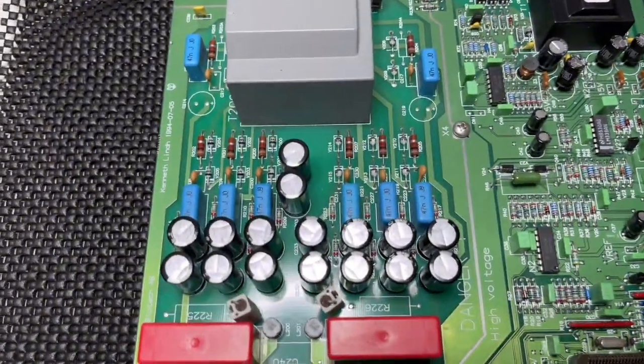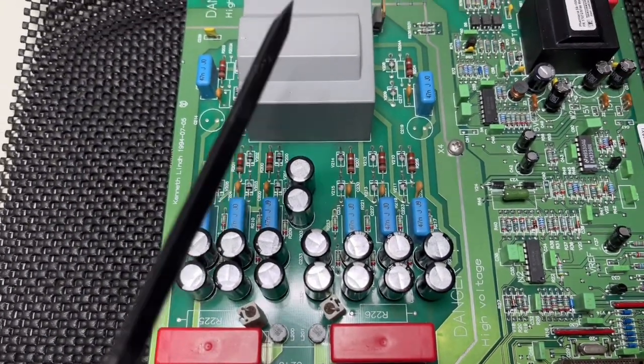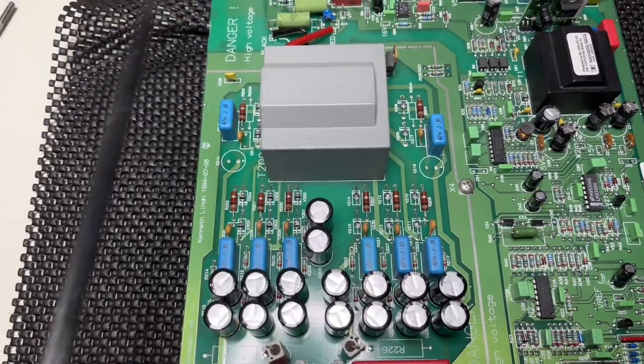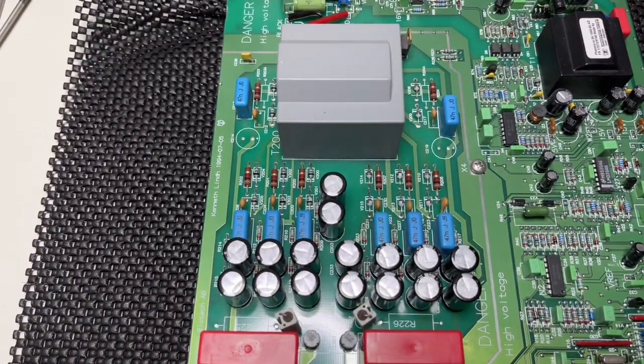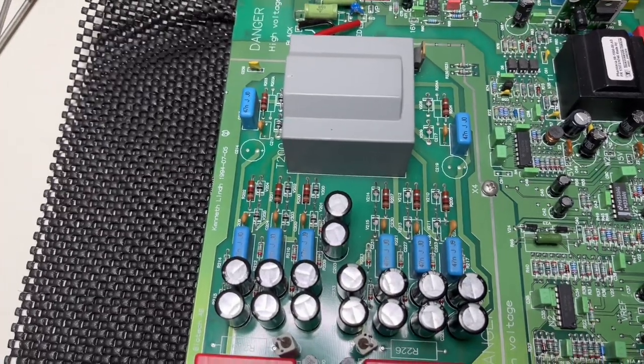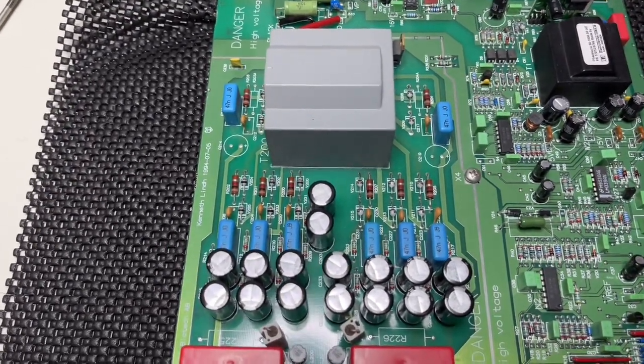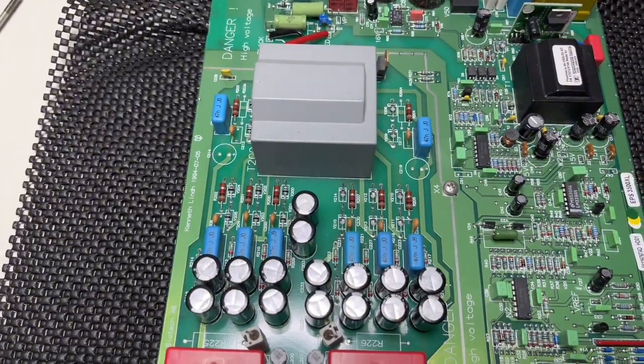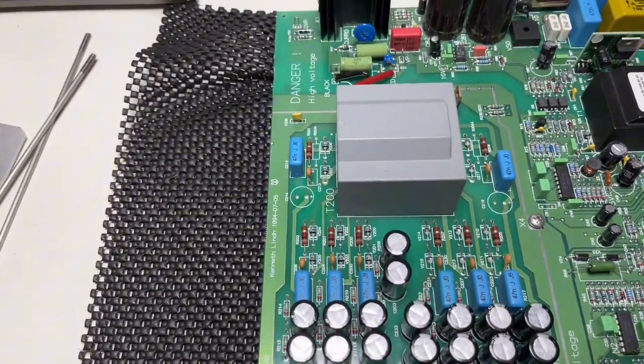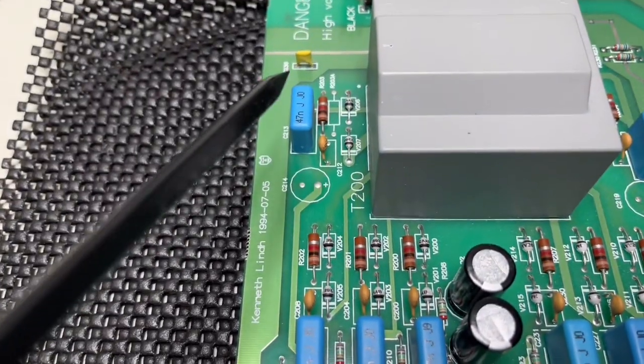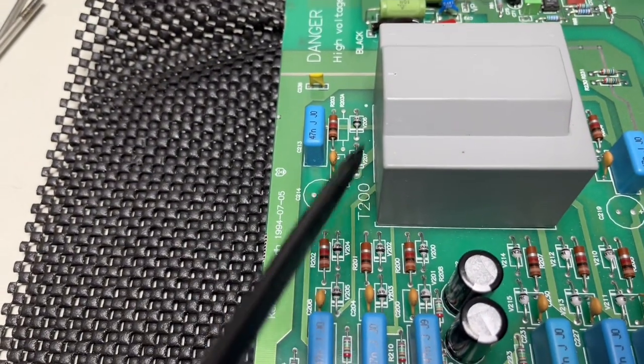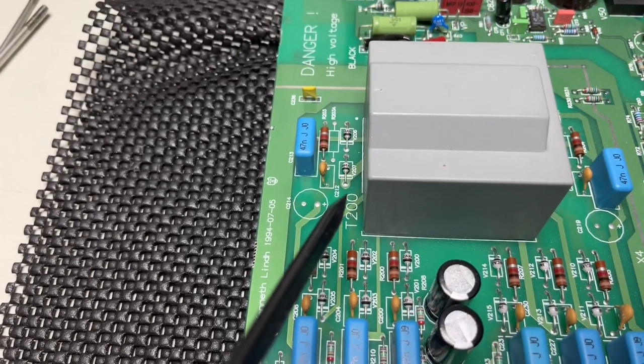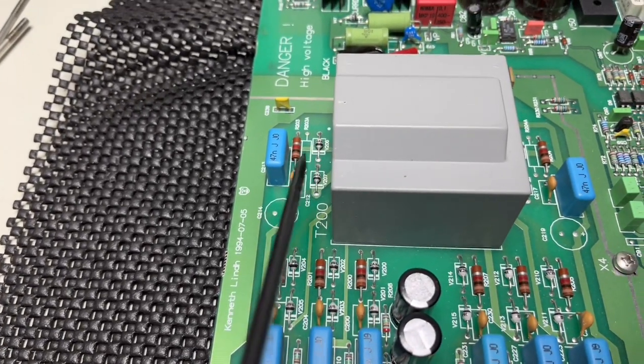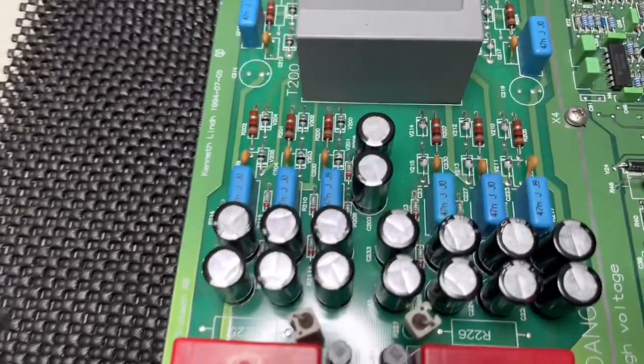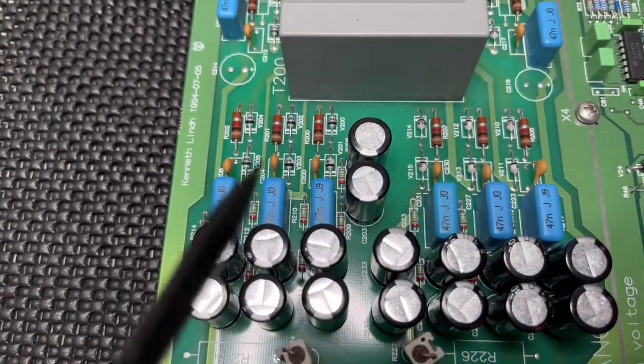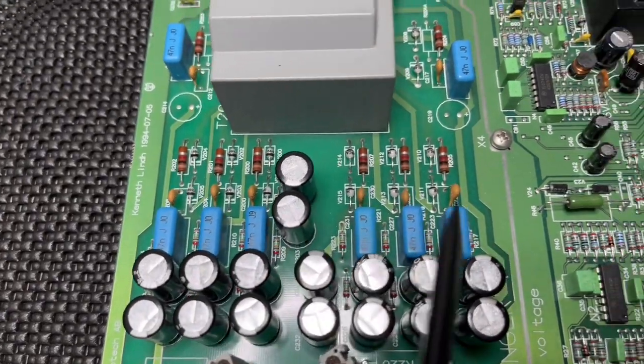The other interesting design is that they use four windings for the positive side and four windings for the negative side. Each winding with a rectification module. For me, this is a module comprised of two high voltage diodes in series and the snubber network. You see here we have the same circuitry 4 times on both sides.